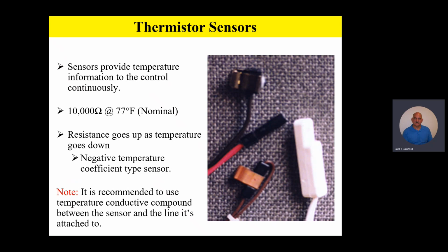The technician can always do this as a nominal calibration point by taking the sensor, removing it from the board, and ohming it out at 77 degrees. It should be around 10,000 ohms or very close to it. It should also be noted that these sensors are a negative temperature coefficient type of sensor, which means the resistance goes up as the temperature goes down.